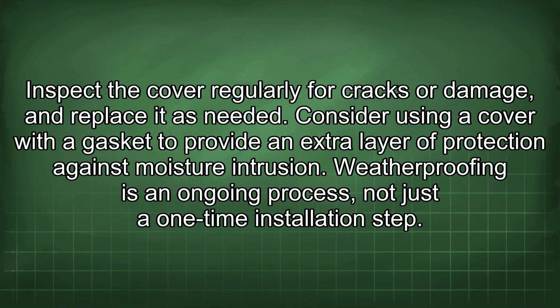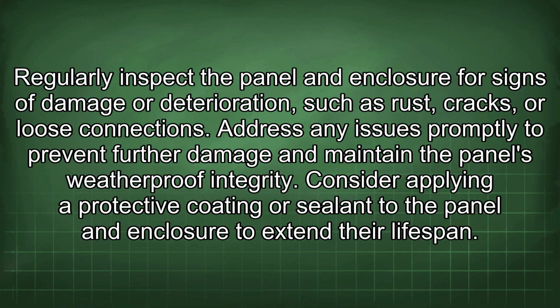Weatherproofing is an ongoing process, not just a one-time installation step. Regularly inspect the panel and enclosure for signs of damage or deterioration, such as rust, cracks, or loose connections. Address any issues promptly to prevent further damage and maintain the panel's weatherproof integrity. Consider applying a protective coating or sealant to the panel and enclosure to extend their lifespan.